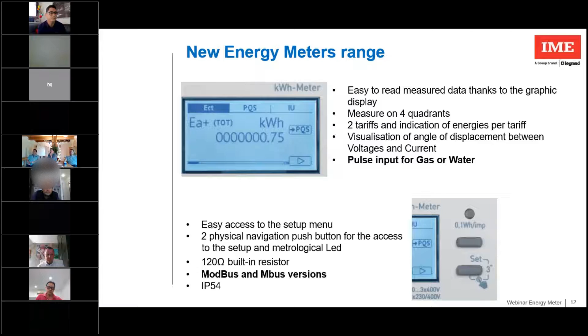As I mentioned, the new range will be available in MID version. This means that the active energy parameter is compliant with EN 50470 in class B. For the not MID version, it is in class 1, compliant to EN 62053. A little explanation about these two norms.